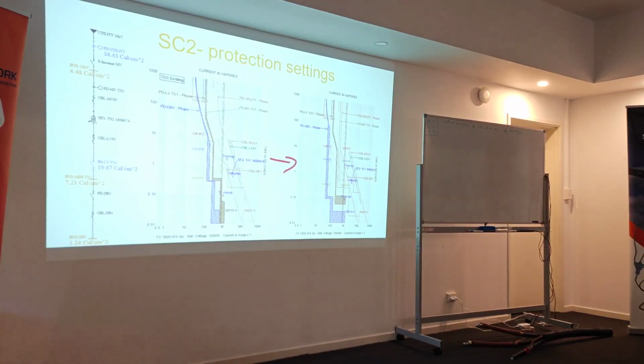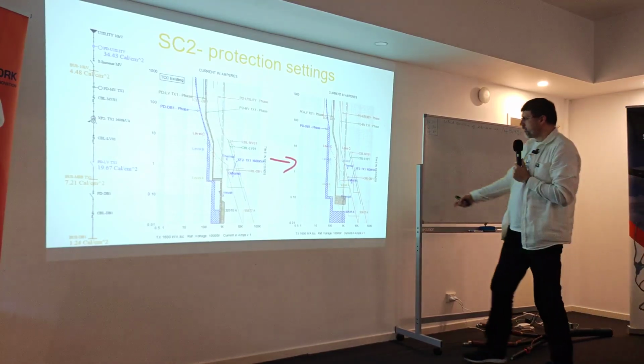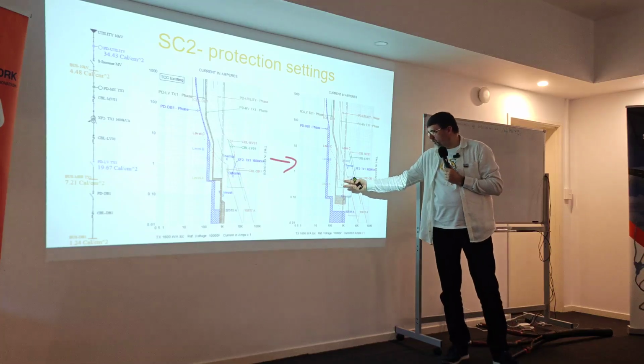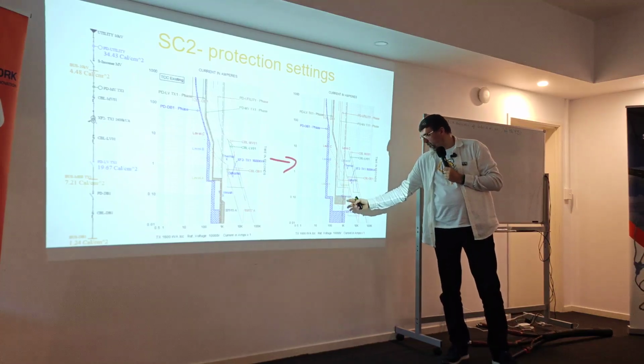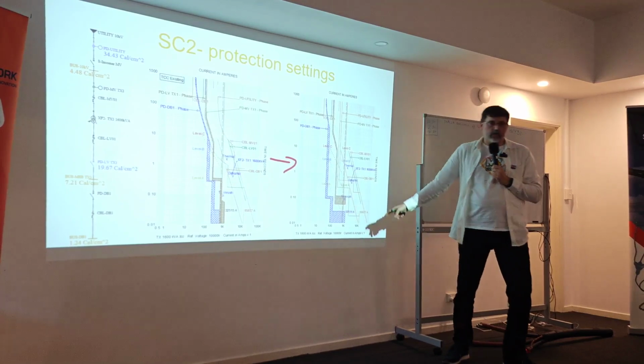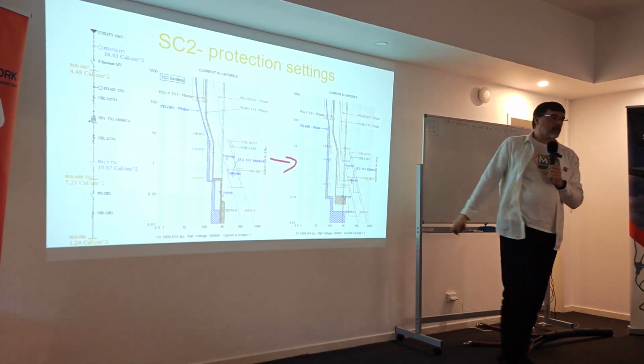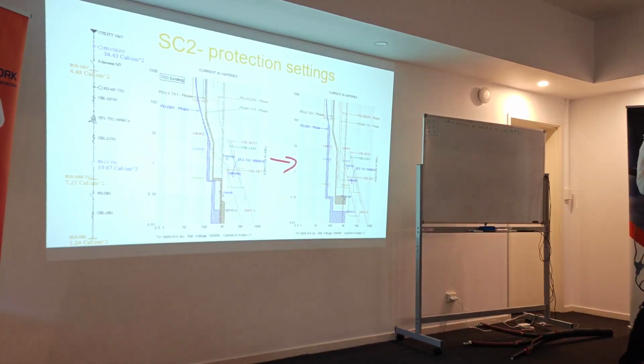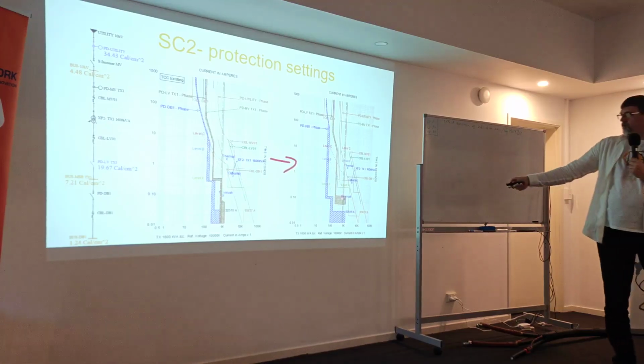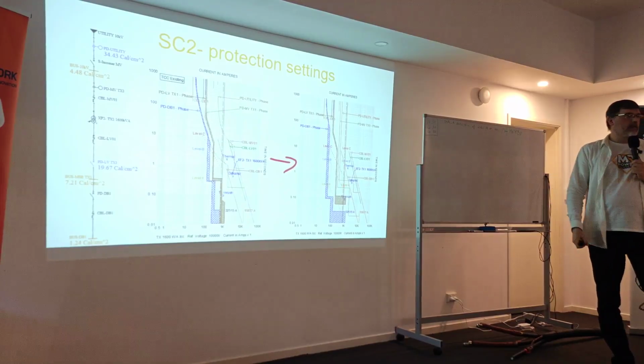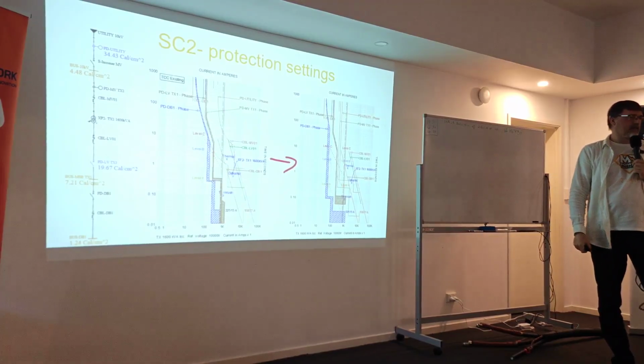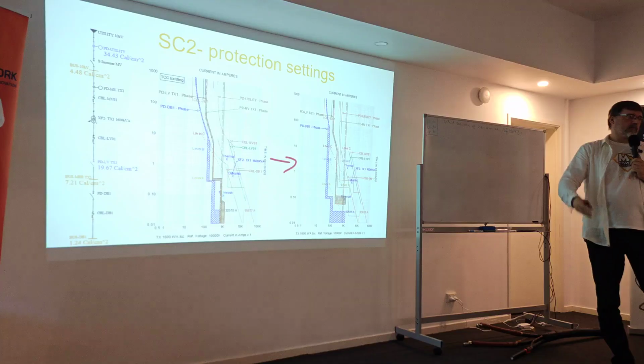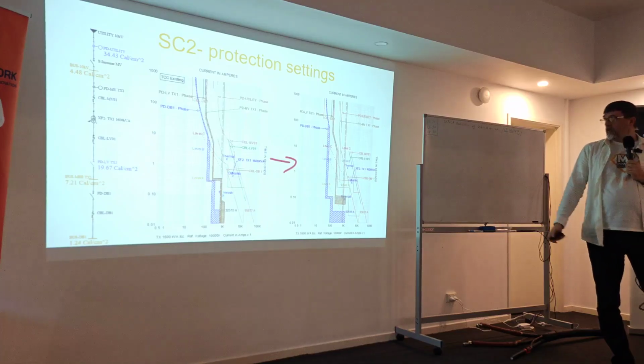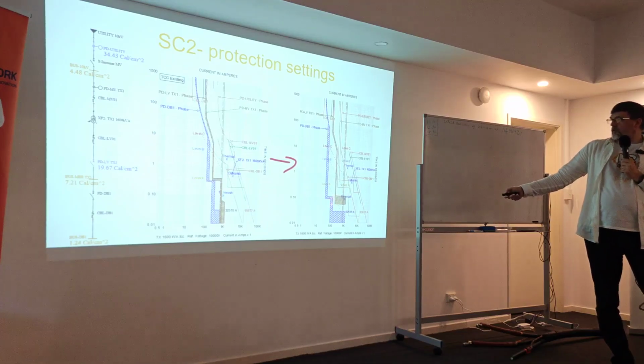Yeah, because there is a minimum, something called critical interval time, which is 200, this is 300 milliseconds, 200, and between this and this is 100. But this one is based on the protection tables, because sometimes you can test this and say if it works by test. And between low voltage and medium voltage, you need at least 200 milliseconds. Proposed is 300 most of the time. You move to the left the PD1, DV1 phase curve. So yeah, we're able to move the other ones to the left.